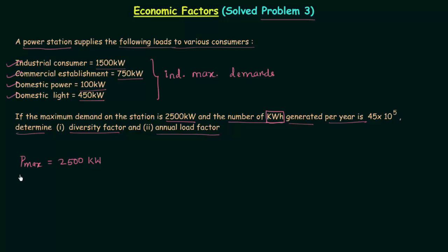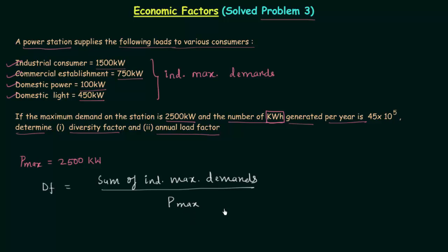Starting with the diversity factor: P_max equals 2500 kilowatt. The diversity factor equals the sum of individual maximum demands over P_max. The sum is 1500 plus 750 plus 100 plus 450, which equals 2800 kilowatt, divided by P_max of 2500 kilowatt, giving 1.12 as the diversity factor. As expected, it is greater than 1.